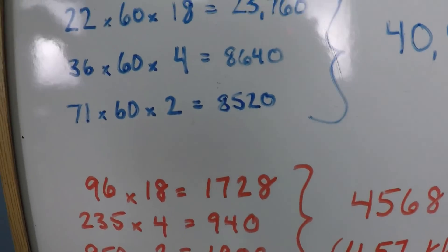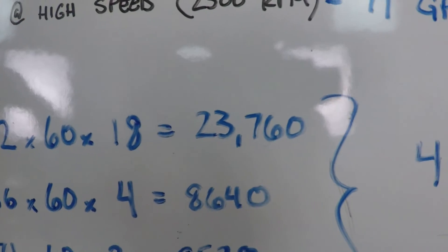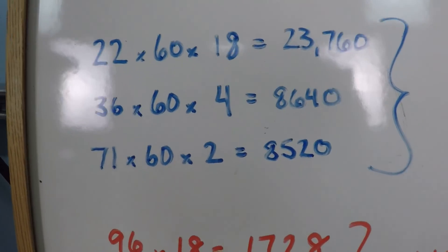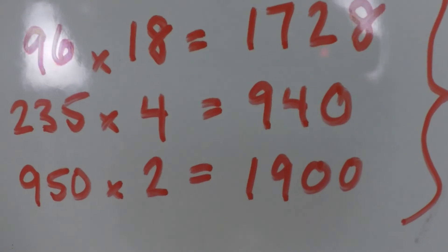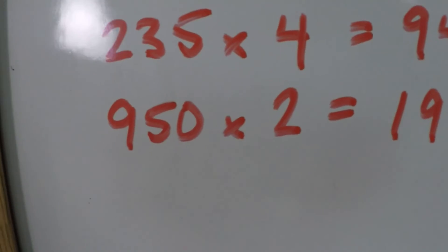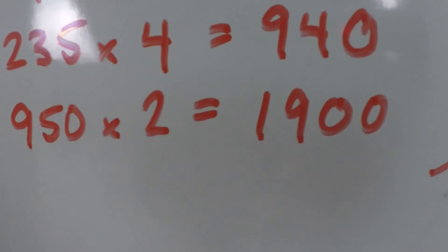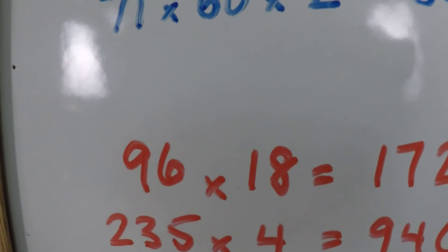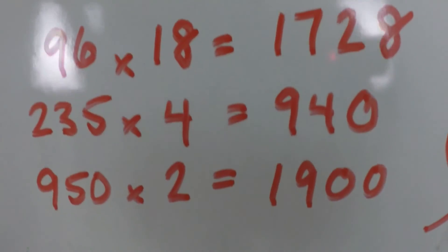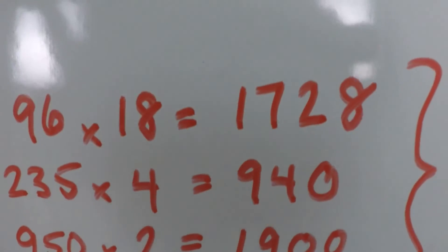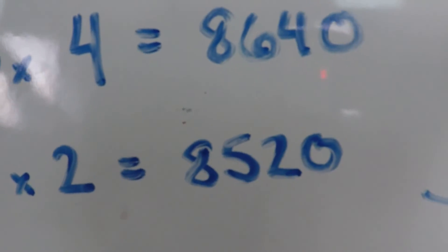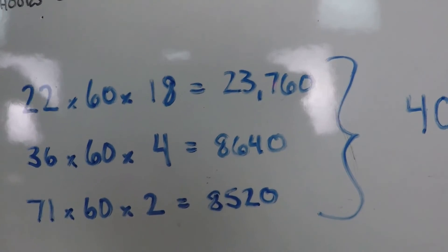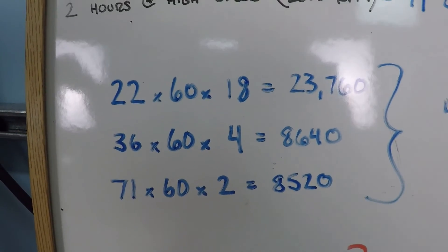Let's take a look at some of the interesting things here. Remember I was saying about that low speed operation: 23,000 gallons from the low speed versus 8 and 8 from the other two. But look at the power consumption here. So at 2 hours at higher speed, not even maximum, but higher speed, you use 1,900 watts of power. 18 hours at the lower speed only use 1,728. So you use more power in 2 hours than 18 hours. You use more power for 8,520 gallons than you do 23,760. That's how variable speed pumps work. That's how you save money with them.